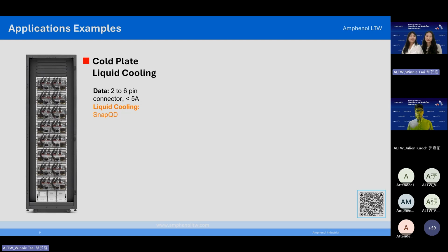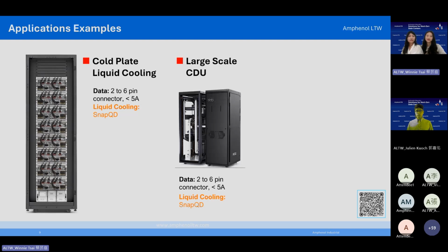On the data side, you can use 2 to 6 pin connectors with rated currents smaller than 5 ampere for telemetry and controls. And for liquid, again, SnapQD, so techs can service supply and return lines quickly without spills.